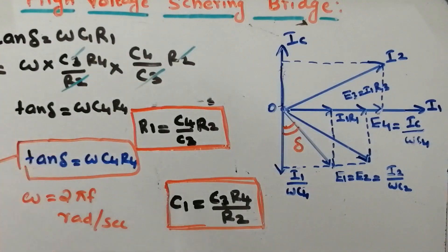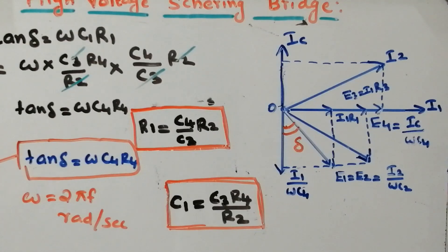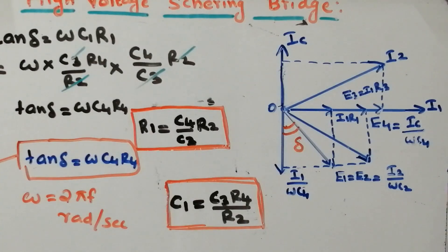Tan delta is known as loss tangent. With the help of loss tangent, you can determine how much heat will be dissipated — that means dielectric loss. Loss tangent and dielectric loss are essentially the same term. This is the way to determine the value of dielectric loss by using high voltage Schering bridge.